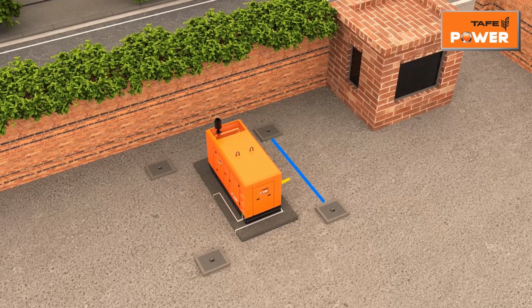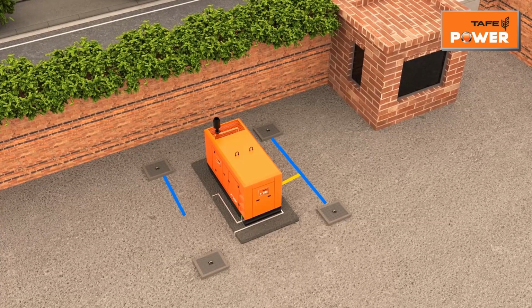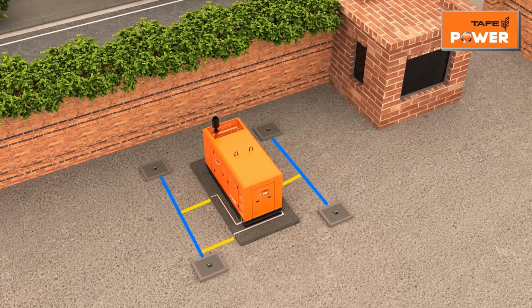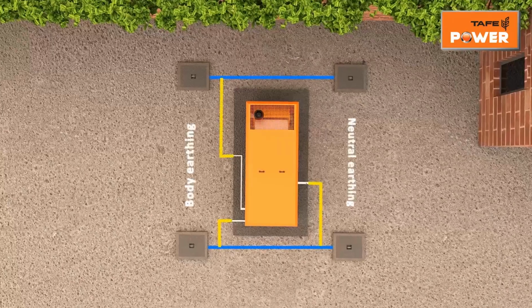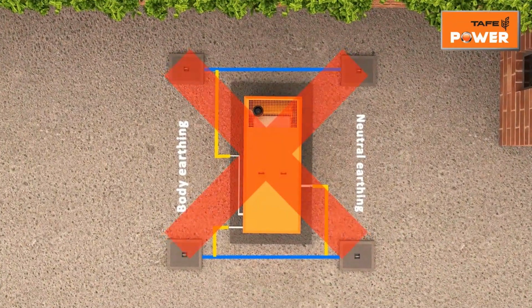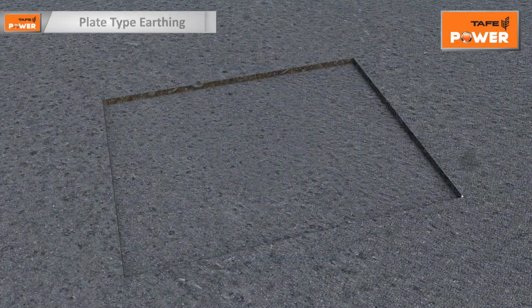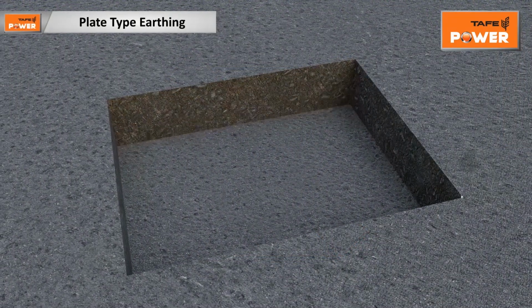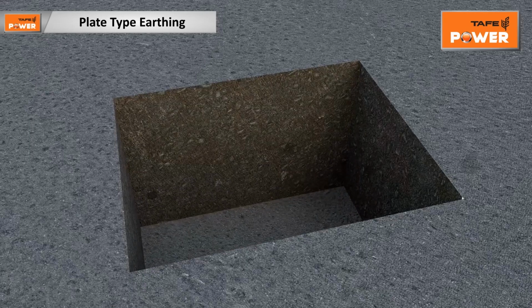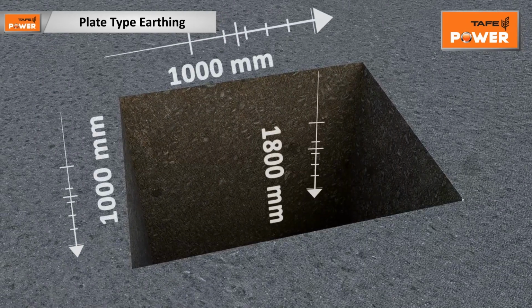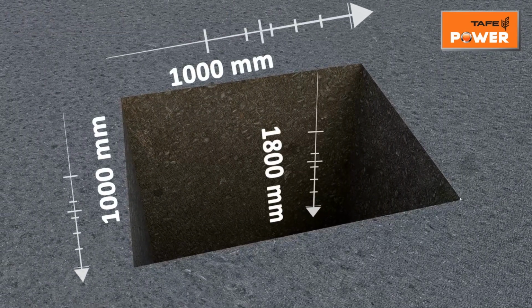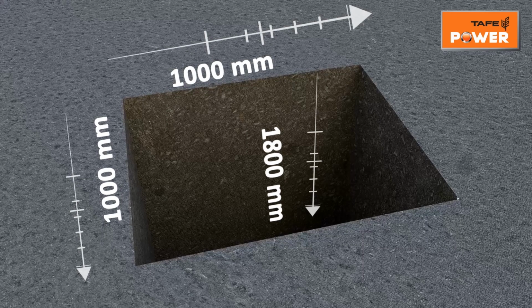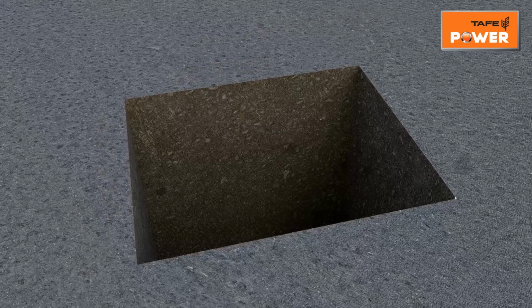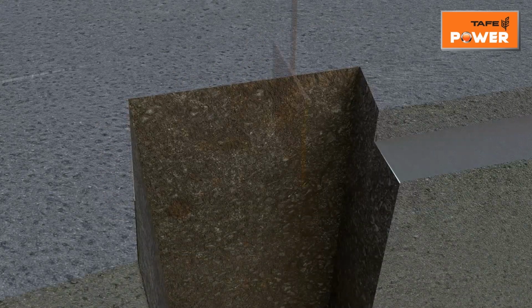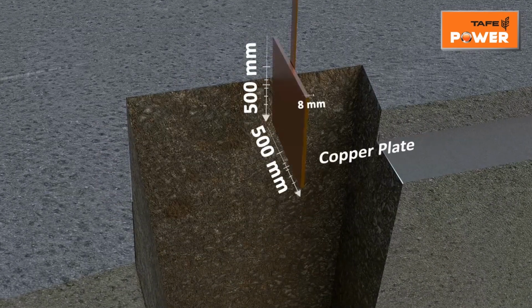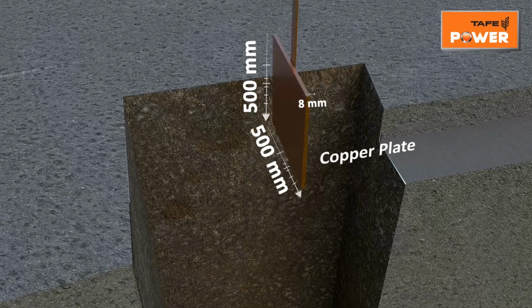Connect the 2 neutral earth pits to form the neutral earth grid. Similarly, connect the two body earth pits to form the body earth grid. Body and neutral earth should never be interconnected. Earthing of genset should be done in accordance with the local regulations. The recommended length and width of earth pit is 1000 millimeters and the depth is 1800 millimeters. The length and width of copper plate should be 500 millimeters and the thickness should be 8 millimeters.